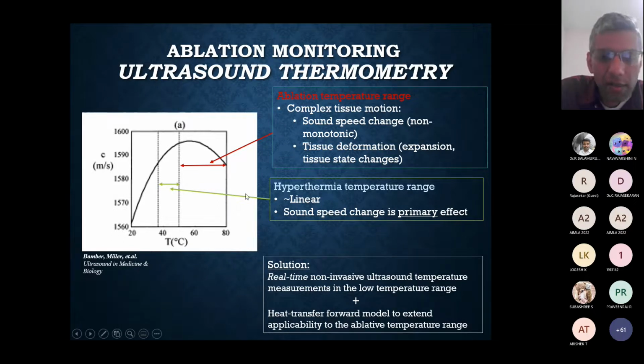Not only that, as you increase the temperature of tissue — which is about 70% water — it undergoes a lot of changes: tissue deformation, coagulation, expansion, and so forth. So tracking motion at higher temperatures becomes a lot more challenging. The question was, for ablation, you have to measure at higher temperatures. Clinicians are interested in measuring temperatures on the order of 70 to 80 degrees. So how can we do that, knowing this limitation in sound speed versus temperature?